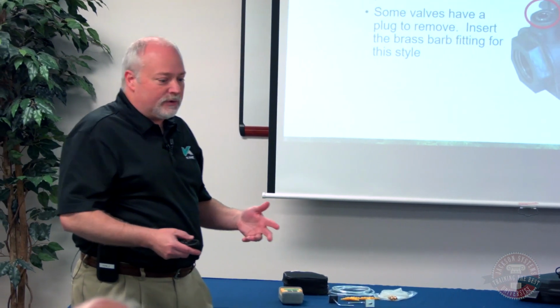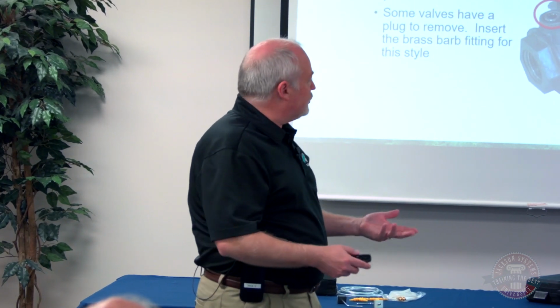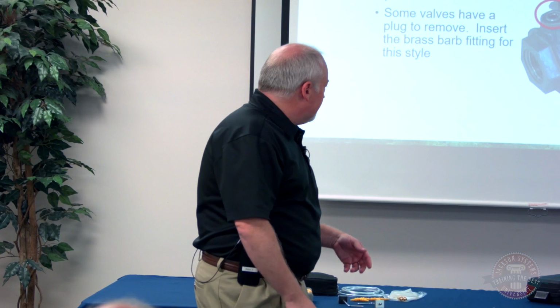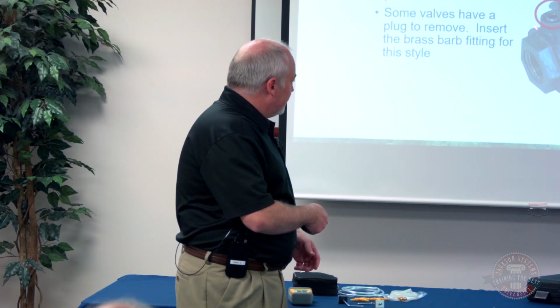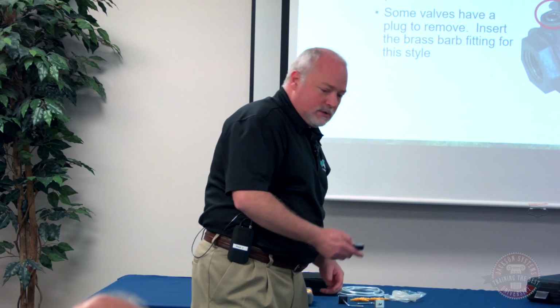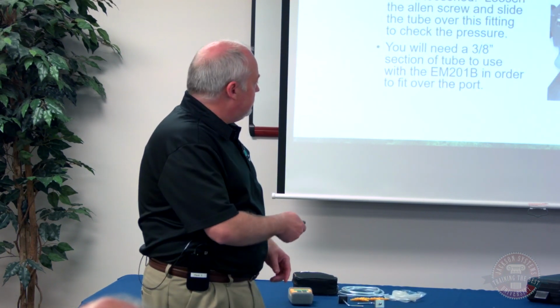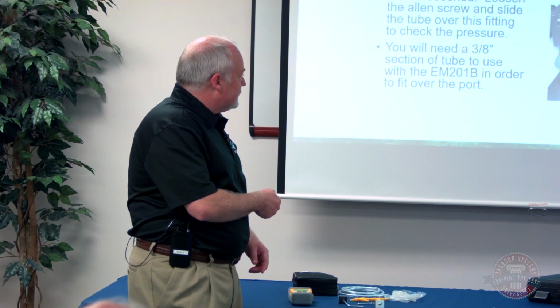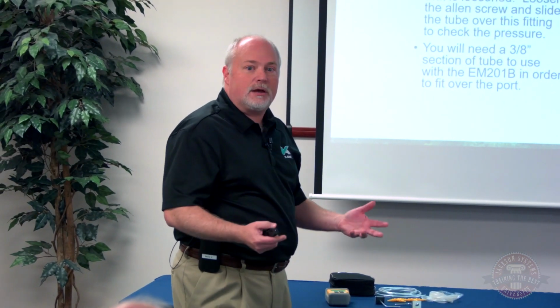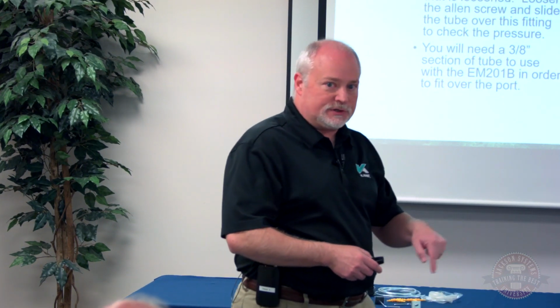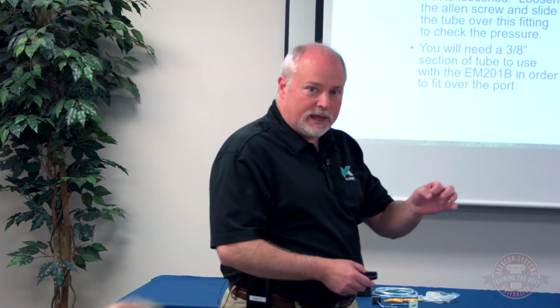So when you think of a digital manometer, a lot of times the first thing that comes to mind is gas pressure, because anytime you install a fuel-fired appliance, you should check your gas pressure. There are a couple of different styles of gas valves in the market. The one that's been around for a long time has a plug that we're going to remove. We're going to insert our brass barbed fitting that's going to screw in place of that plug so we can check that gas pressure. But some of the newer valves don't have a removable plug. Instead, they've got just an Allen screw that we're going to loosen, and it doesn't have to come all the way out in order to check our gas pressure. So you just loosen that up a few turns so that some of the gas can escape.